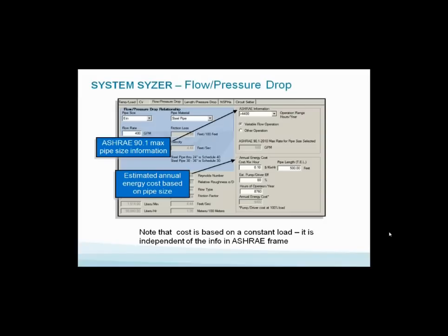You will find this Windows-based version of the System Syzer includes this in the pipe sizing. When you go to flow and pressure drop, you have a right-hand column that says ASHRAE information. You've got to plug in how many hours a year you think you're going to run your pump and pick whether it's variable flow or other operation. Once you've done that, it will not allow you to pick a pipe too small per ASHRAE 90.1 2010. This will make you meeting the ASHRAE codes easier, very easily done.